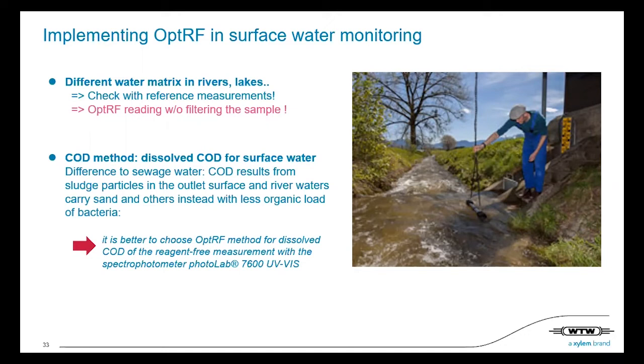Therefore, you can measure both, because you leave the sample in the same cuvette and measure with two methods. So it's an easy way, you can do both. But at the end of the day, our experience is that the method for dissolved COD is the best method for surface water.